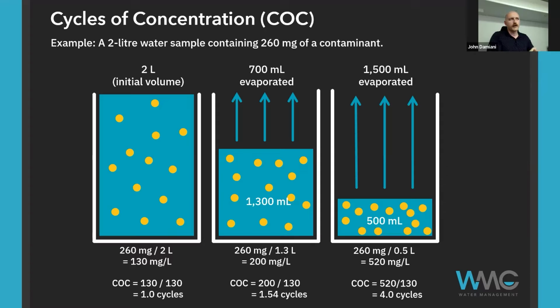So if we were to evaporate 700 mils from that initial 2-liter sample, we'd have 1,300 mils left. So now our live sample is 1,300 mils or 1.3 liters. We still have that same 260 milligrams, because what we're evaporating is only the pure H2O. Effectively, if we were to condense the evaporate and test it, there would be 0 milligrams of that contaminant in there because it's just evaporated pure water. So all we've done is subtract the volume, but we have the same amount of contaminant. 260 milligrams again, divided by 1.3 liters. Now we're at 200 milligrams per liter of concentration. So for our cycles of concentration, we take our current sample, the 200, and divide that by the 130 that we started with, because that's our fresh makeup. So we're at just over 1.5 cycles.